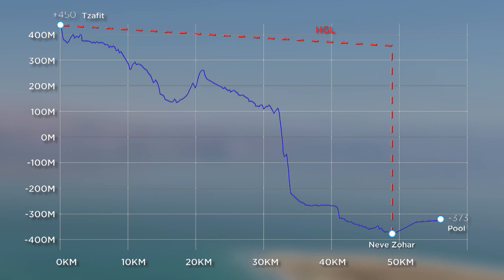This nature reserve needed to be preserved, which meant that the pipeline had to be buried underground and could not be accessed for maintenance and repairs. Second, there is an 830-meter height difference between the reservoir and the Dead Sea pools. This brought about the need for a unique solution that could reduce the 83-atmosphere upstream pressure to a 5-atmosphere downstream pressure, in a widely varying flow rate of 50 to 1,200 cubic meters per hour, and in a very small area.